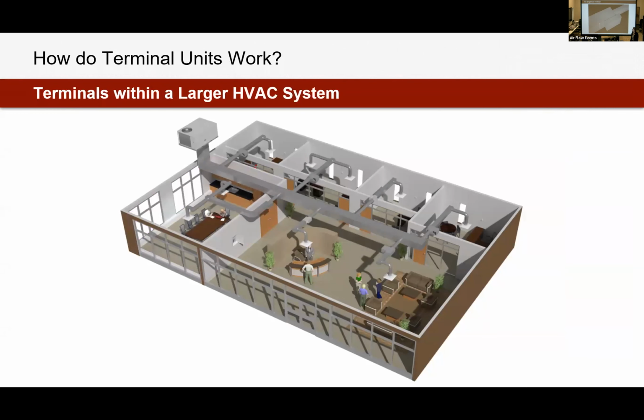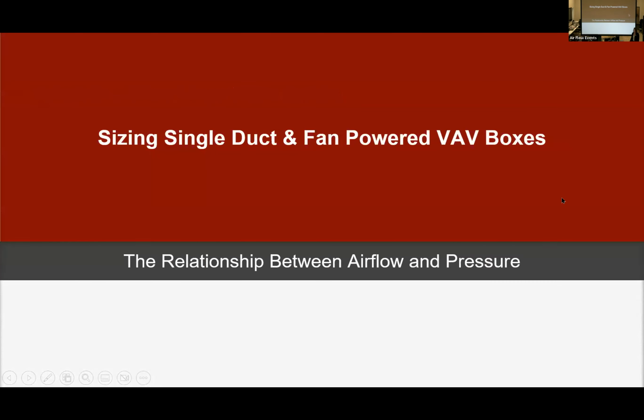So as was mentioned earlier, we can use single ducts to create zones in our space. In this big office building here, in the back corner, we've got one independent office, and we have a single duct up in the duct stream. That little blue box there is a single duct terminal unit. It is going to be changing the volume of air into that single independent office.